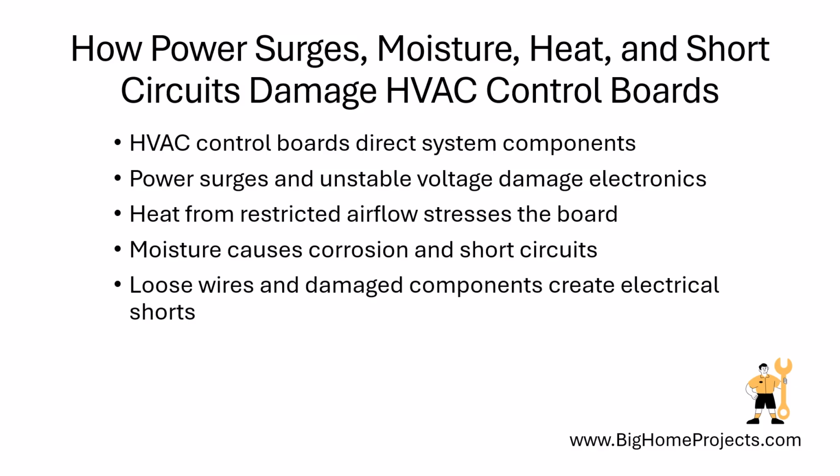Loose wire connections may produce heat and sparks, while a damaged motor, compressor, or solenoid can send a short circuit back to the board. One lesser-known cause is static electricity during installation or service, which can damage sensitive components even when no mark is visible.